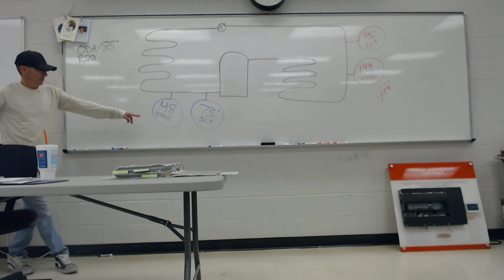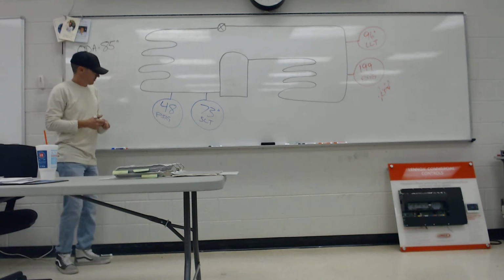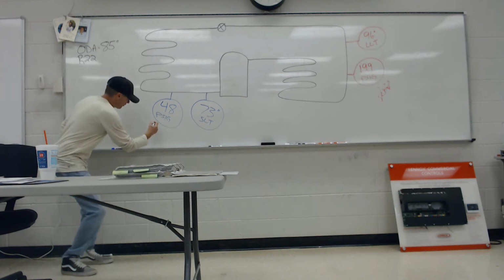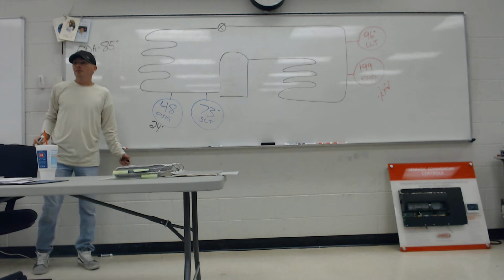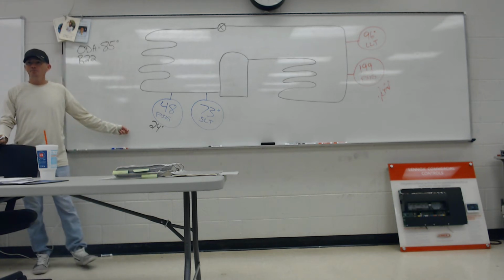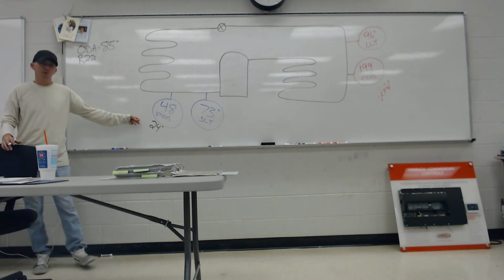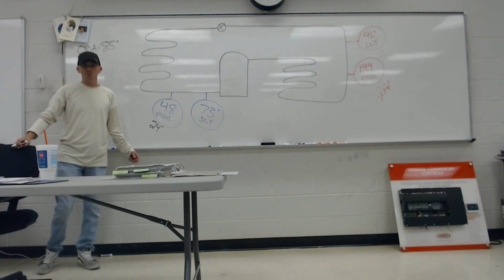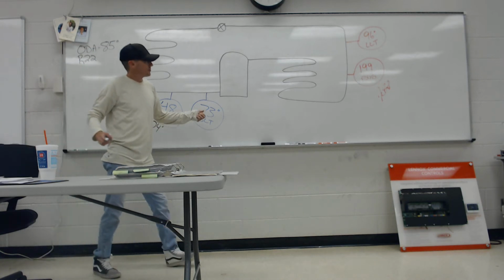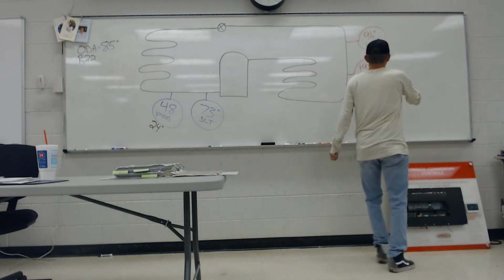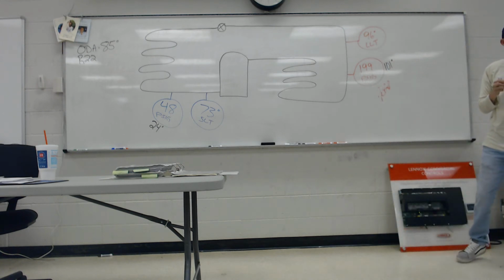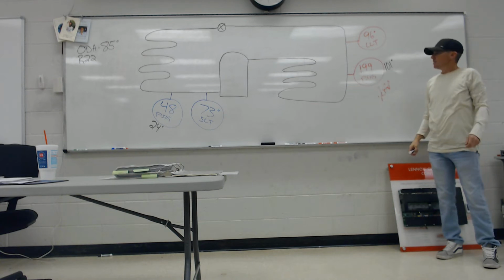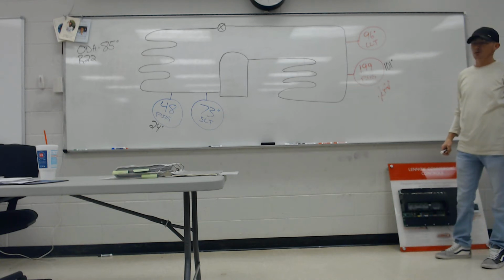Let's convert these real quick. What's 48 converted? 24. 24 degree evaporator. Straight off the bat, y'all realize that's a red flag? We're below 32, so any humidity in the airstream is going to start sticking to that coil. We're going to start frosting. We're going to freeze up the coil. Red flag. What's 199 converted? 101. So I'm condensing at 101 degrees. I'm evaporating at 24 degrees. Y'all want any more information?